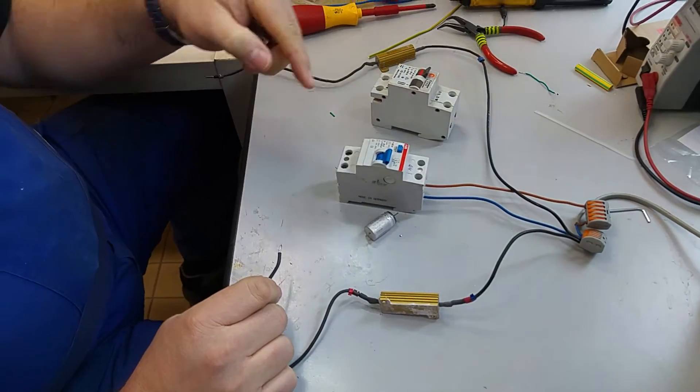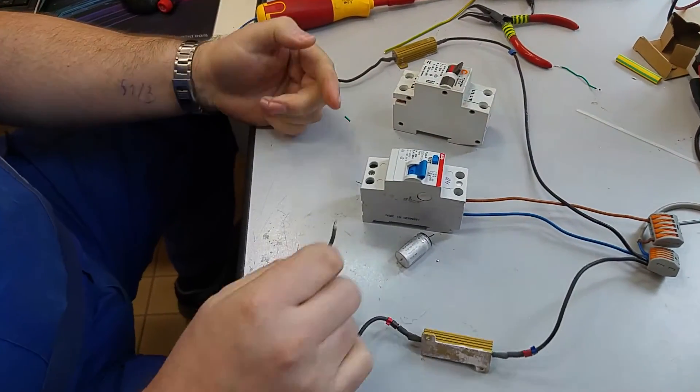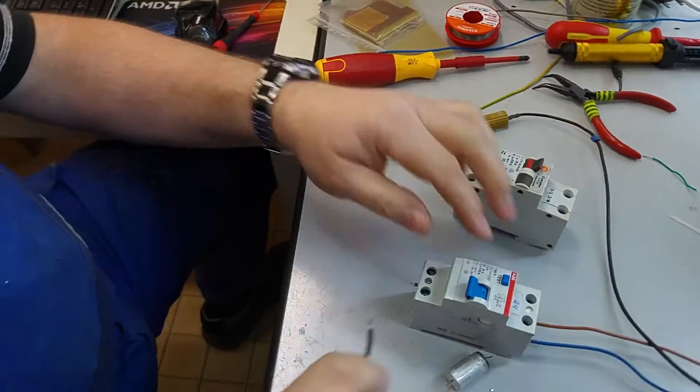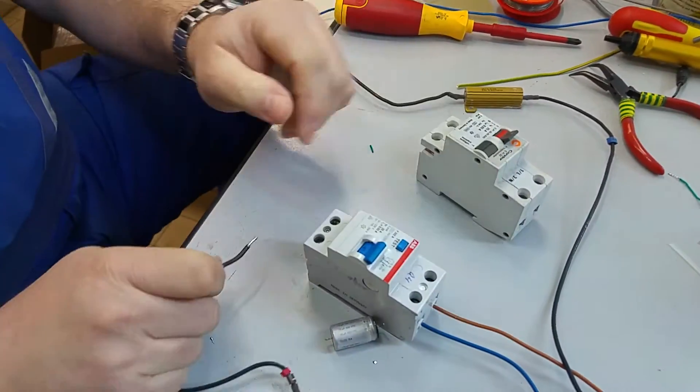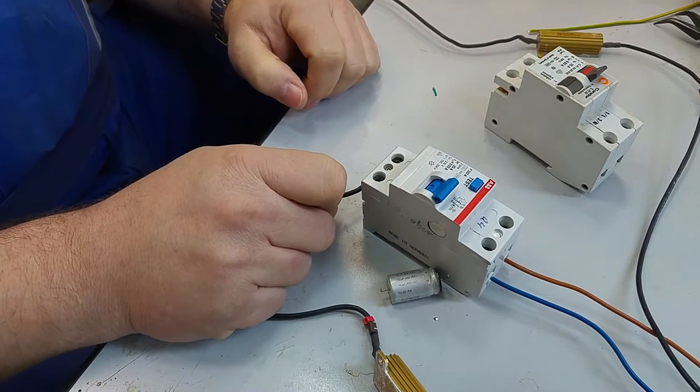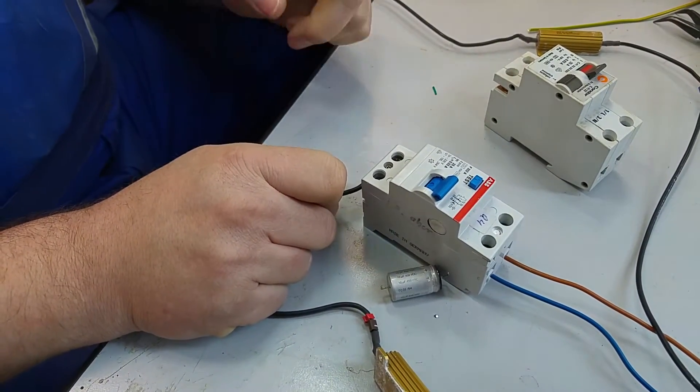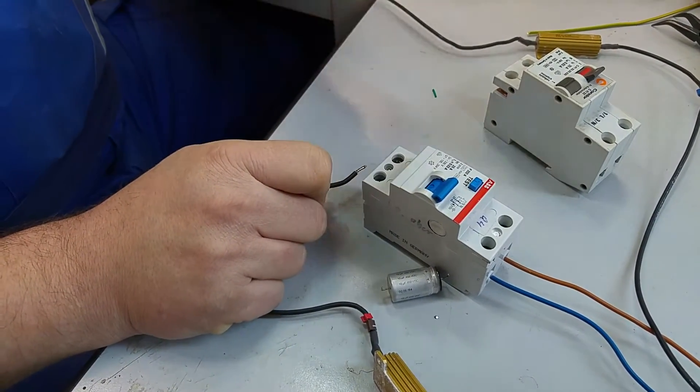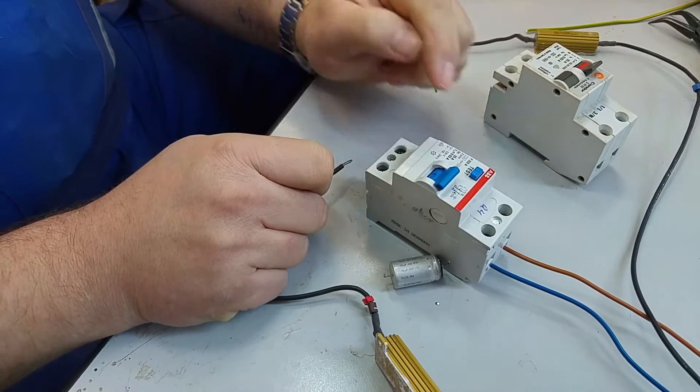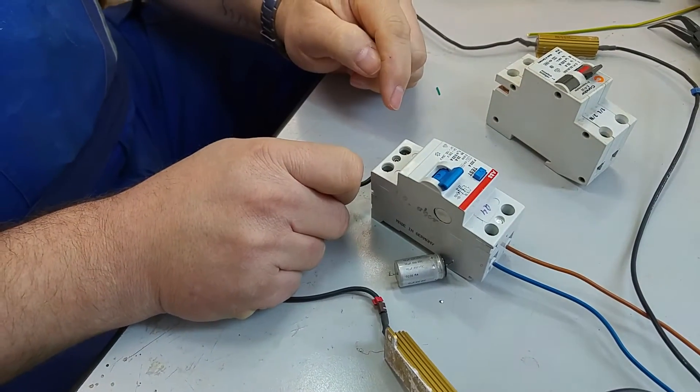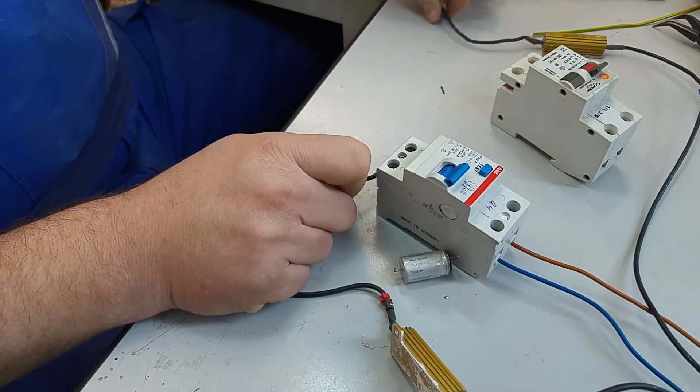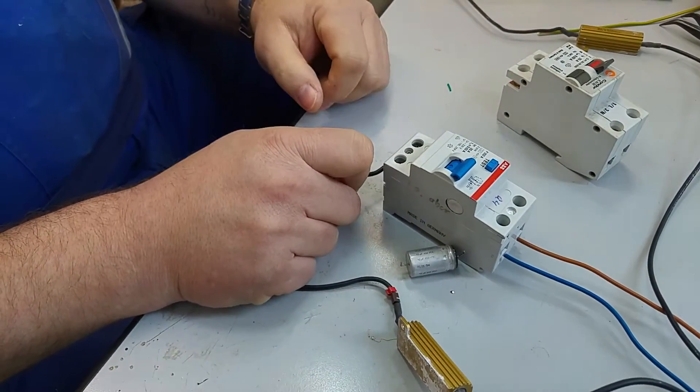RCD is on, diode is in. It trips. Now after the diode, it doesn't trip. It should trip, it's marked to trip with pulsating DC, but it just doesn't trip.